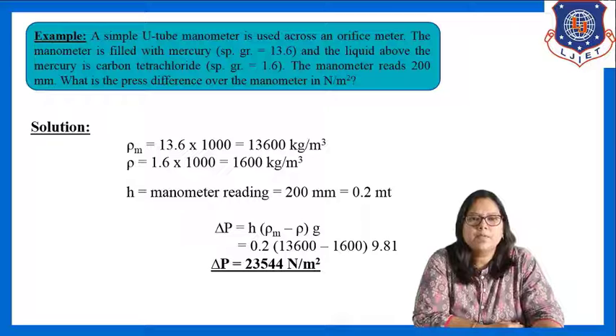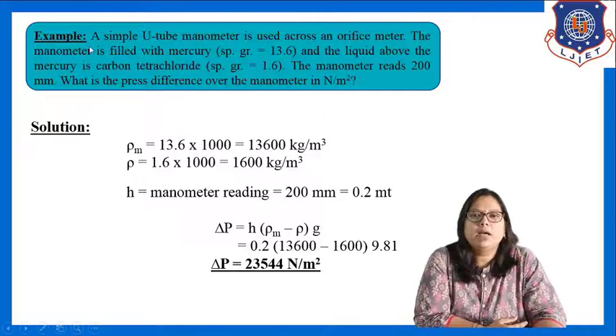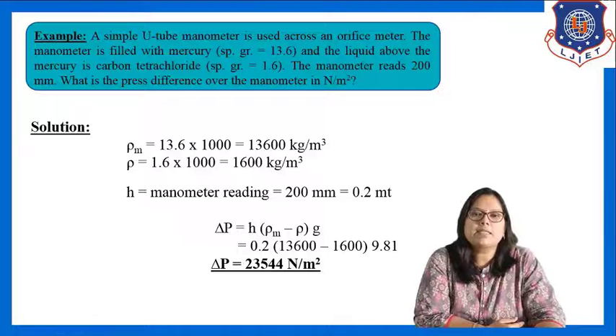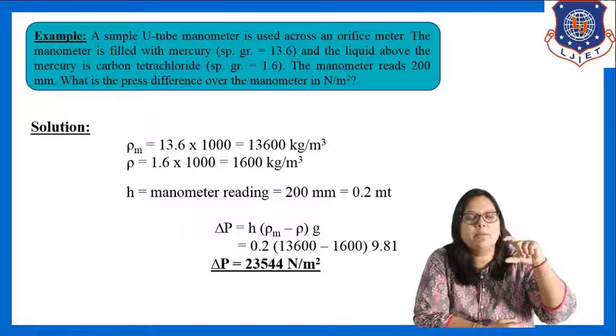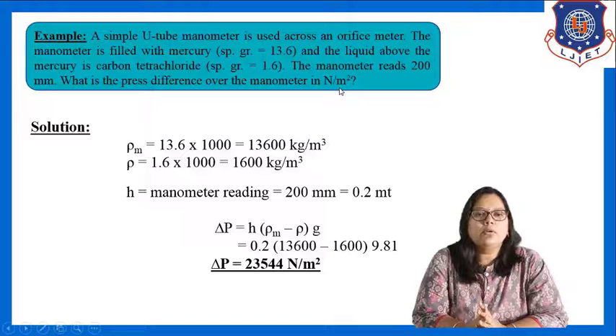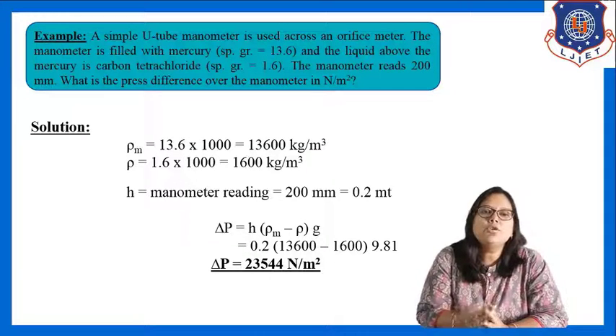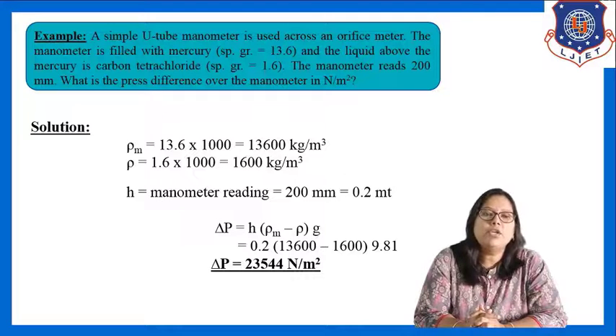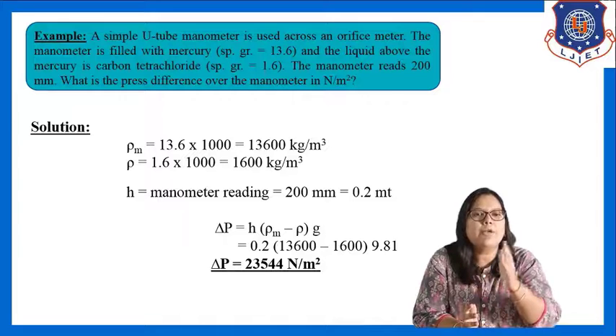Now let us take one example. A simple U-tube manometer is used across an orifice meter. The manometer is filled with mercury having specific gravity 13.6, and the liquid above the mercury is carbon tetrachloride (the process fluid) having specific gravity 1.6. The manometer reads 200 mm. What is the pressure difference in Newton per meter square? We directly use the equation: ΔP = h·(rho_m − rho)·g.